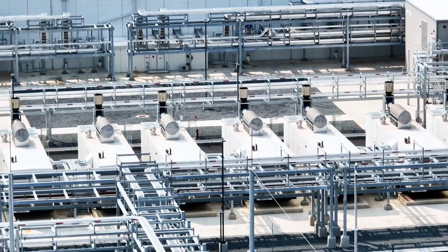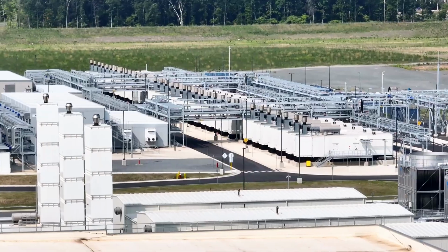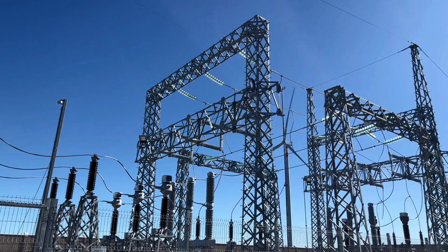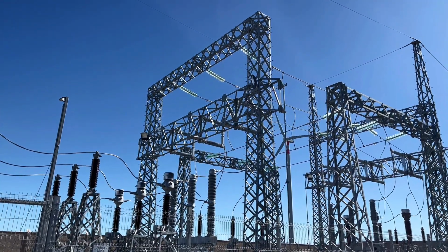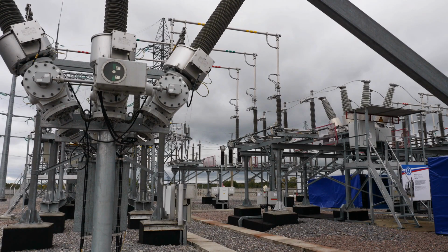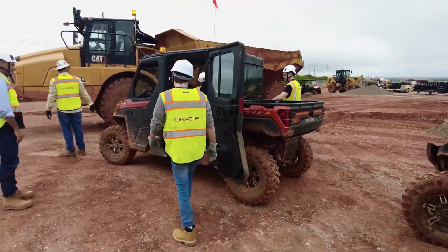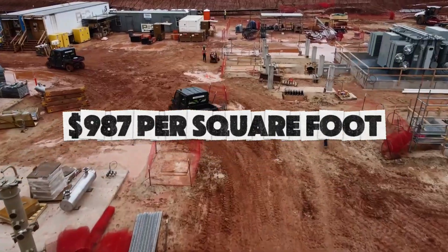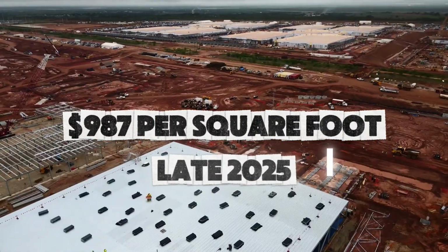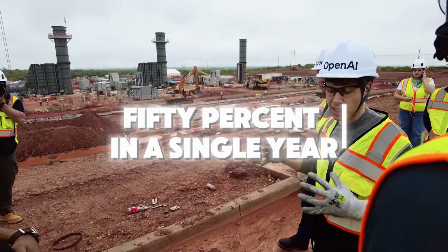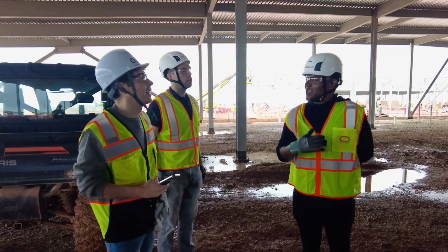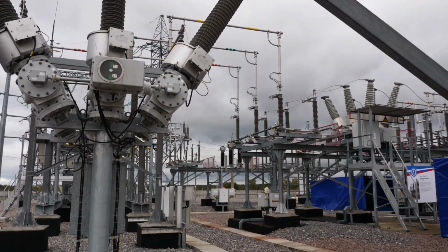The third wall is equipment. Transformers now carry 2 to 3 year lead times from major manufacturers because every data center project on Earth hit the supply chain simultaneously. Construction costs hit $987 per square foot by late 2025, up 50% in a single year, driven almost entirely by electrical equipment scarcity.